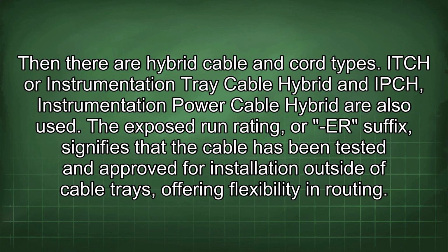Then there are hybrid cable and cord types. ITCH, or instrumentation tray cable hybrid, and IPCH, instrumentation power cable hybrid, are also used. The exposed run rating, or ER suffix, signifies that the cable has been tested and approved for installation outside of cable trays, offering flexibility in routing.